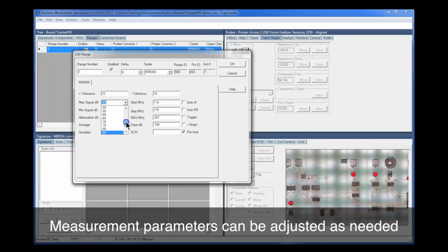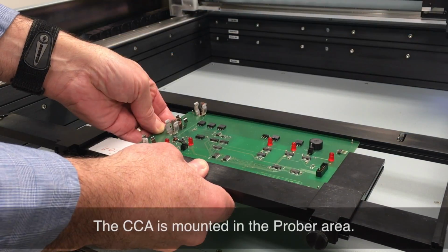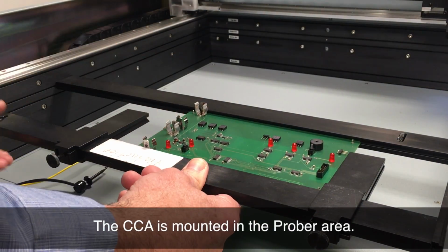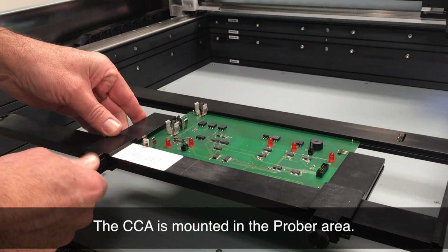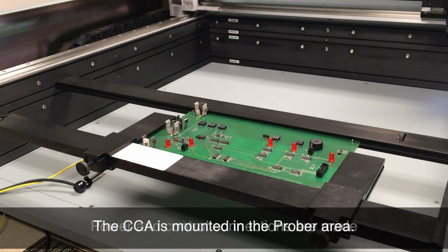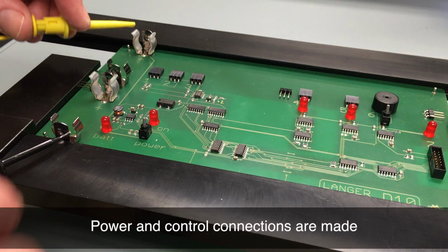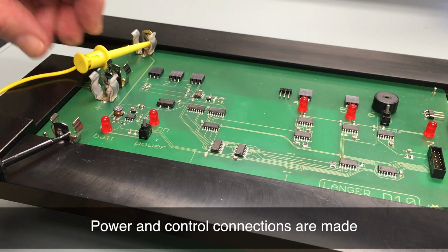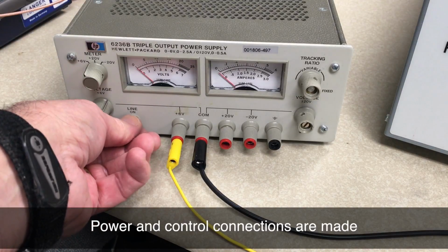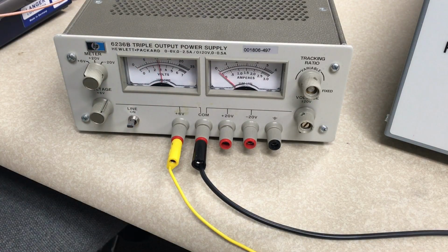In the range dialog, you can edit parameters such as minimum and maximum signal level, attenuation, start and stop frequency, resolution bandwidth, and measurement comparison floor. Once the test points are created in the database, the CCA is mounted within the prober test bed. Provisions for getting the CCA in a powered on state are necessary for capturing live RF measurements. These provisions are designed and implemented by the end user.